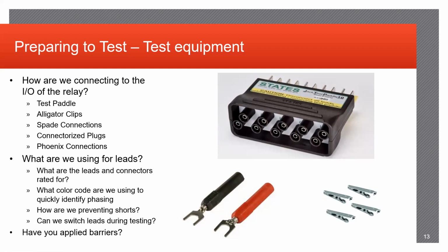Color coding, I think, is a big deal as well. It helps when you're relay testing. You may be plugging in quite a few leads and test terminals, so being able to quickly identify what lead is going where and what purpose it's serving is extremely important. For example, when I was out in the field doing relay testing, I would use a red, white, blue system for A, B, and C phases. I would use those for both the currents and voltages and make sure that they're separated well enough to correctly identify which one's the current and which one's a voltage. Just something like that makes for good practice when you're testing relays.